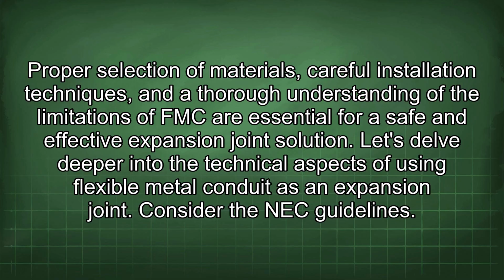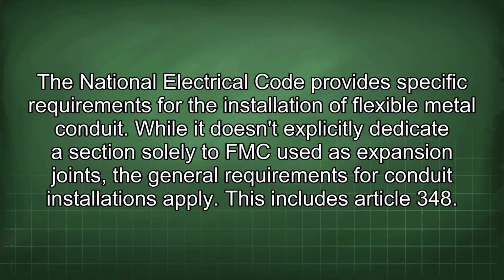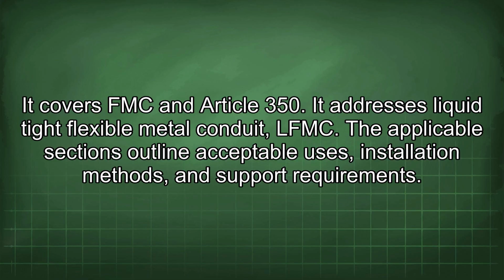Let's delve deeper into the technical aspects of using flexible metal conduit as an expansion joint. Consider the NEC guidelines. The National Electrical Code provides specific requirements for the installation of flexible metal conduit. While it doesn't explicitly dedicate a section solely to FMC used as expansion joints, the general requirements for conduit installations apply. This includes Article 348. It covers FMC. Article 350 addresses liquid tight flexible metal conduit, LFMC. The applicable sections outline acceptable uses, installation methods, and support requirements.